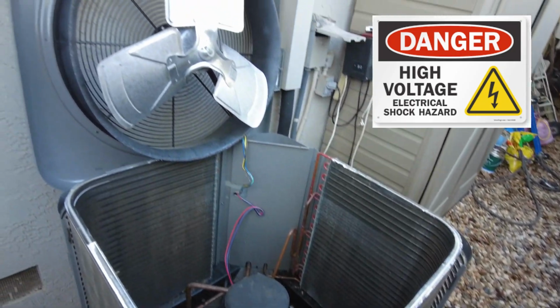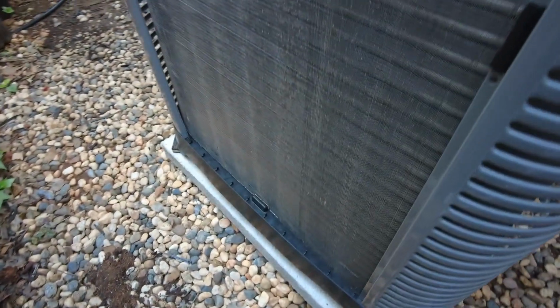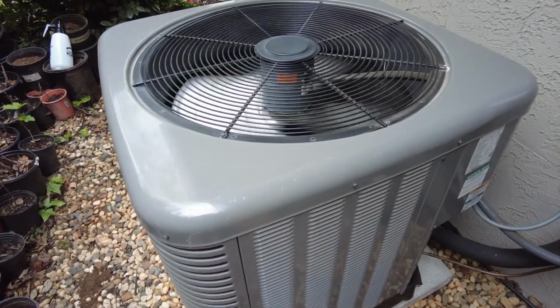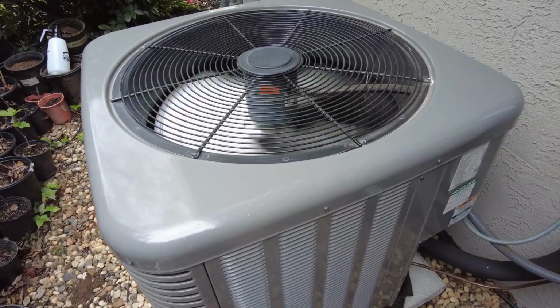or death. So we've completed the cleaning and we can clearly see that the dirt and debris on the coils are now gone. When we go down inside the unit and look from the inside out, we can see daylight, which tells us air can pass through those coil fins and allow the air to be in contact with the tubing, which is where we're going to release the heat. Units packed together, ready to go, clean, efficient, and reliable, ready for the Sacramento summer heat.